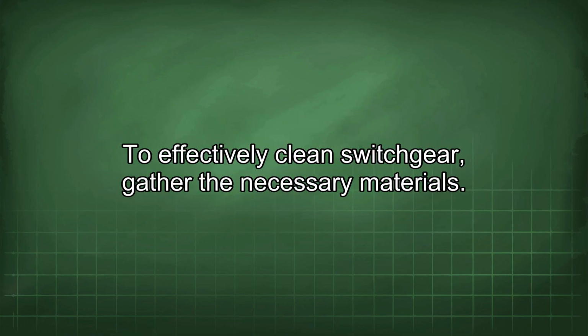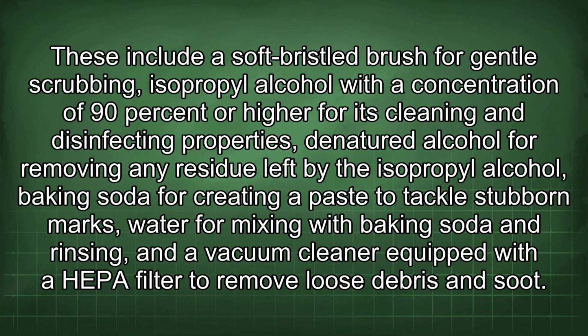To effectively clean switchgear, gather the necessary materials. These include a soft bristle brush for gentle scrubbing, isopropyl alcohol with a concentration of 90% or higher for its cleaning and disinfecting properties, denatured alcohol for removing any residue left by the isopropyl alcohol, baking soda for creating a paste to tackle stubborn marks, water for mixing with baking soda and rinsing, and a vacuum cleaner equipped with a HEPA filter to remove loose debris and soot.